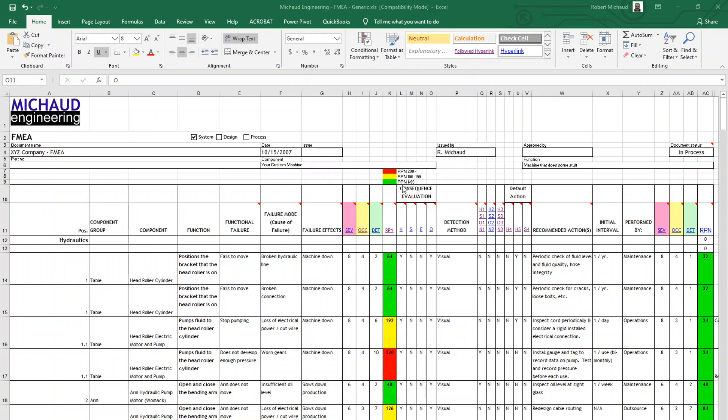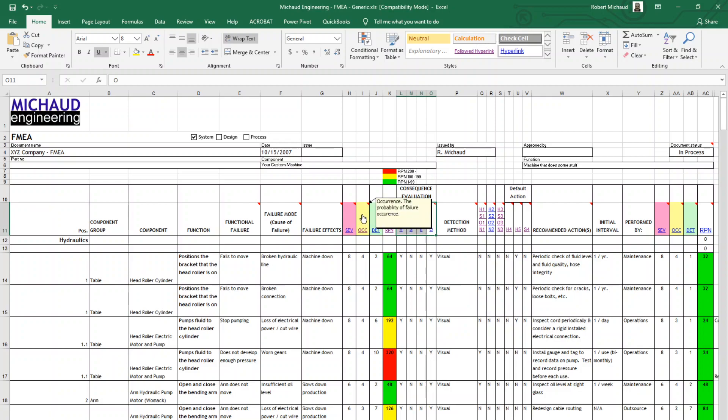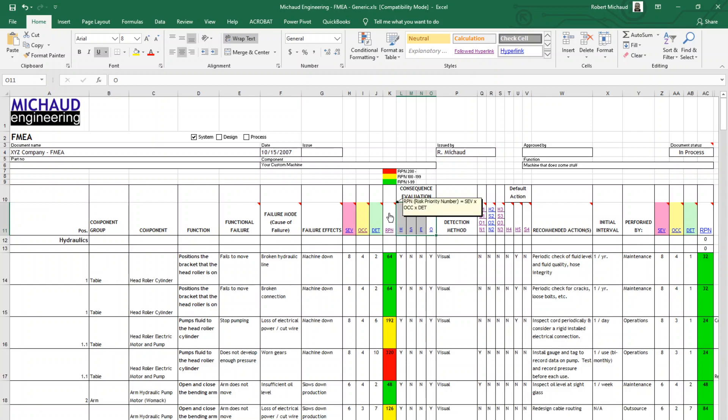From there, we're going to look at these ratings right here. Each one of these grading criteria is used to determine how severe, in this case, how serious the failure is. In this one right here, it's the probability of that failure to occur. This column is going to grade the detection or the risk of not detecting it in the future. Each one of these factors goes into calculating this right here, which is the RPN or risk priority number. This is important because it tells you how risky it is or how severe this particular failure mode is in the overall operation of that machine.